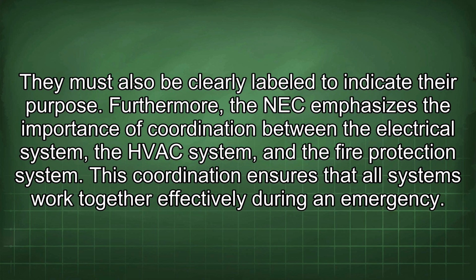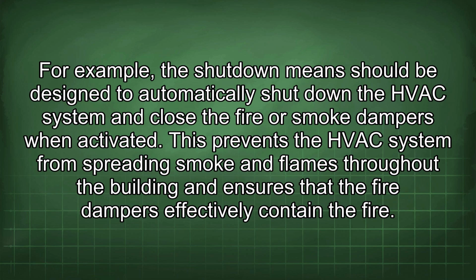Furthermore, the NEC emphasizes the importance of coordination between the electrical system, the HVAC system, and the fire protection system. This coordination ensures that all systems work together effectively during an emergency. For example, the shutdown means should be designed to automatically shut down the HVAC system and close the fire or smoke dampers when activated. This prevents the HVAC system from spreading smoke and flames throughout the building and ensures that the fire dampers effectively contain the fire.